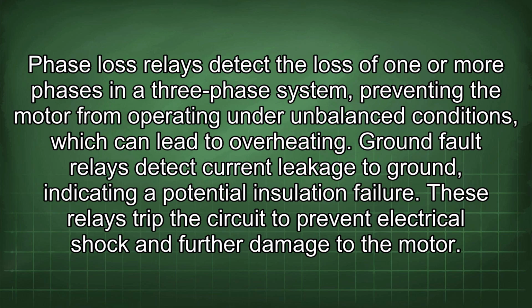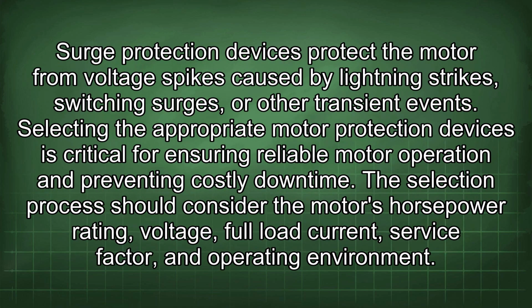These relays trip the circuit to prevent electrical shock and further damage to the motor. Surge protection devices protect the motor from voltage spikes caused by lightning strikes, switching surges, or other transient events. Selecting the appropriate motor protection devices is critical for ensuring reliable motor operation and preventing costly downtime.